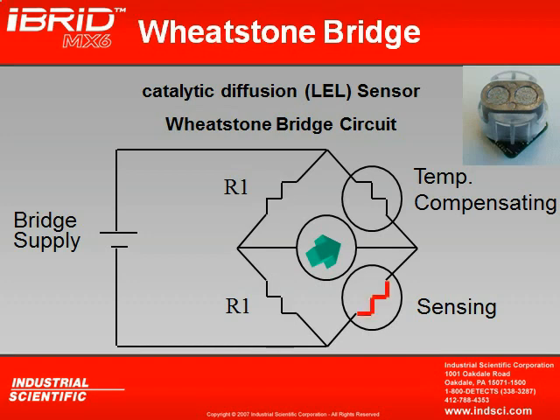But when the sensing bead starts to physically burn the gas, heat's going to build up in this part of the bridge. Not only will heat, so will the resistance. So now my resistance is higher here at the sensing bead than anywhere else on my bridge, causing my Wheatstone bridge circuit to become unbalanced, which is what gives me the reading on the display of my instrument. Alright, so what do we need to know about the combustible sensor and how it detects combustible gas? The way it detects combustible gas is it burns the combustible gas. The greater the concentration of combustible gas, the greater the burn. The greater the burn, the greater the heat. The greater the heat, the greater the resistance. The greater the resistance, the greater the reading on the display.